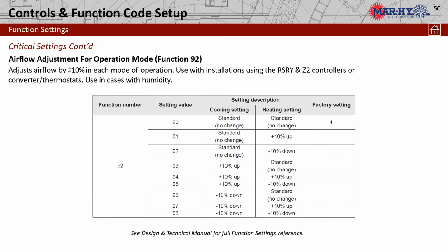92, function 92. This is plus or minus 10% airflow. So if we need to increase our airflow in heating, if we need to decrease in heating, or increase in cooling and decrease in heating. There's a variety of things. As you can see, we've got 8 different selections, eight different combinations of airflow up, airflow down, no change, plus change, minus 10, plus 10. Start off with 0, 0, no change. Looks to me like that's going to be our standard setup.